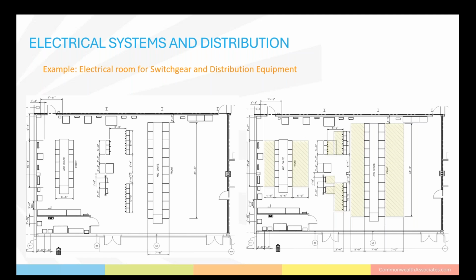Sufficient height needs to be allowed in the room to ensure adequate movement and operation of the equipment. In practice, a room height of 12 feet is a good rule of thumb to start. Depending on the type of switchgear, this may need to be increased to allow for the exhaust of arc gases during fault conditions. In this case, we utilized an arc chute that exited through the roof.